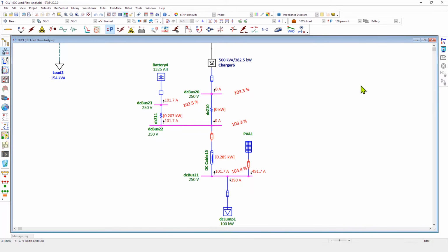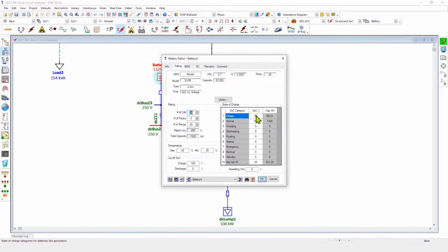For DC short circuit, the typical approach is to run DC short circuit analysis and observe the fault current at various locations or buses or nodes in the system in order to size protective devices such as circuit breakers and fuses. This is typically done on a worst case basis since we are sizing the equipment. However, there may be situations such as running arc flash calculations where you may want to vary the state of charge of the battery. We have already gone ahead and entered some state of charge inside our battery that varies from 50, 100, and 25%.